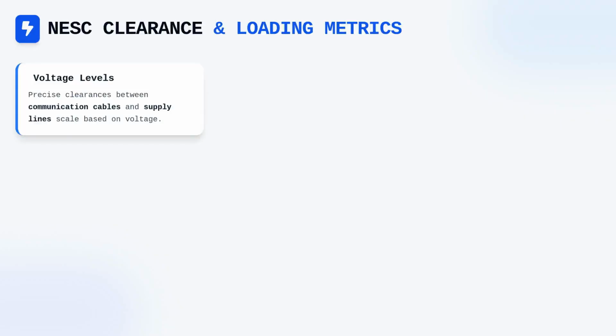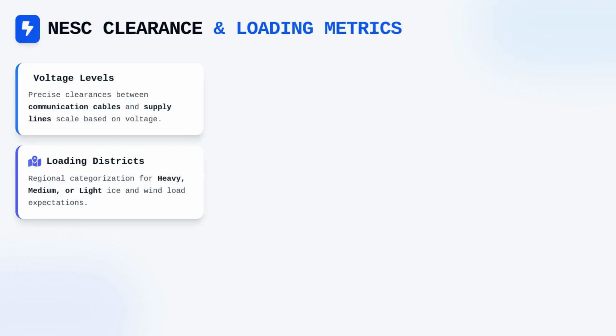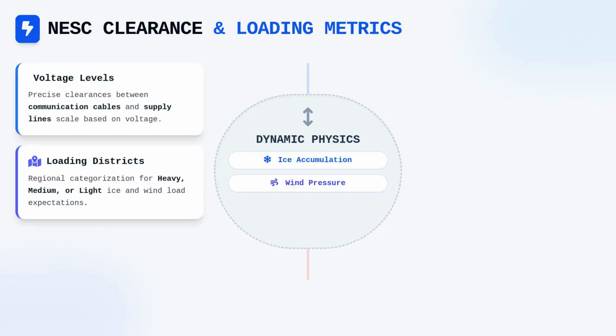One of the most critical aspects of the NESC involves the precise clearance metrics required for aerial and underground installations. When you design an overhead crossing, you must meticulously calculate the clearances between communication cables and supply lines, keeping in mind that these distances change based on voltage levels. These requirements are not static. They are highly sensitive to NESC loading districts, which categorize geographic regions based on expected heavy, medium, or light ice and wind loads. You must account for how environmental stressors affect sag and tension on messenger wires, as a cable that meets clearance requirements on a sunny day may violate them during an ice storm.